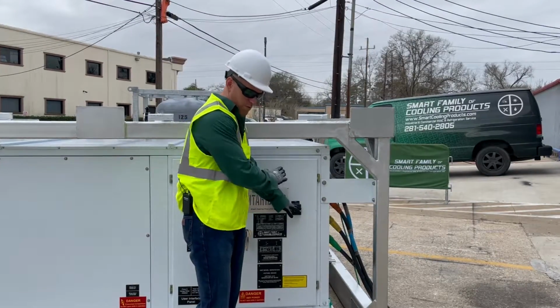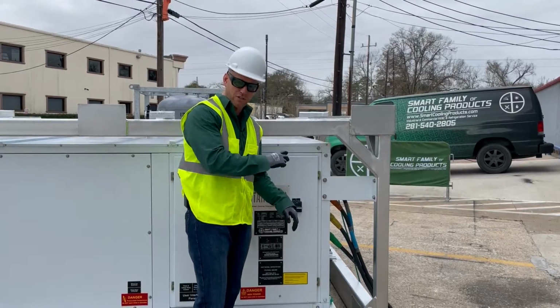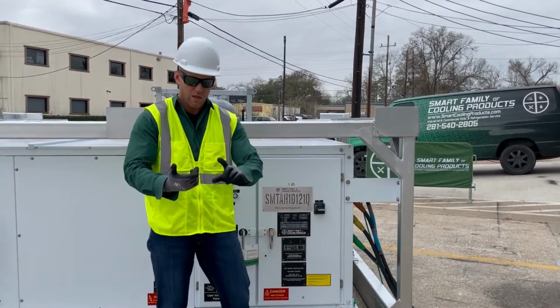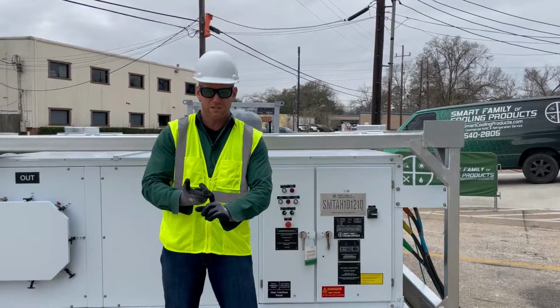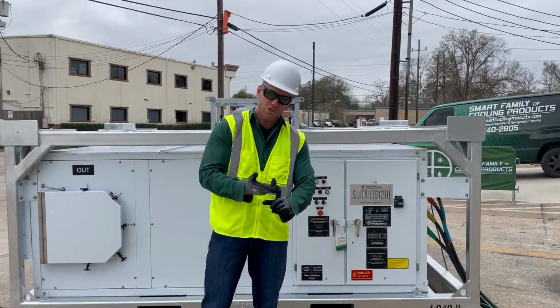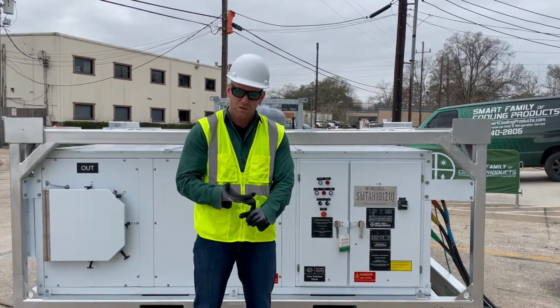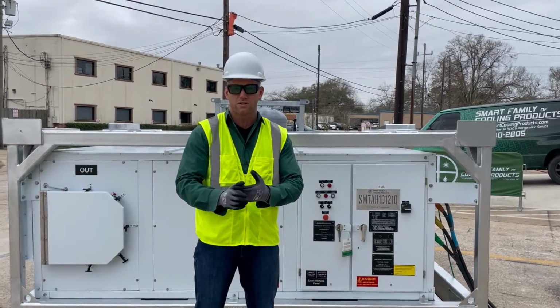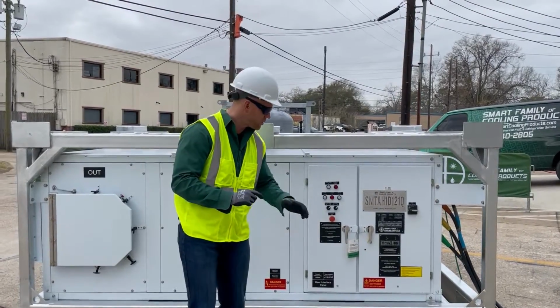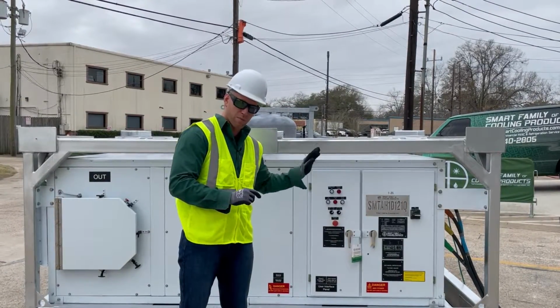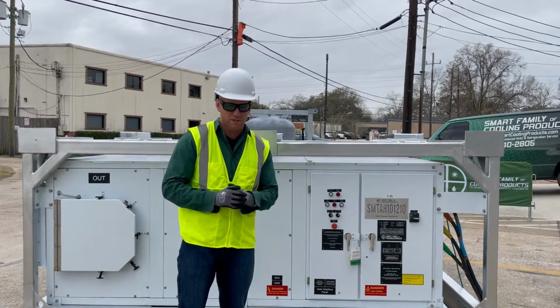Now, there's lots of different means of electrical safety or electrical protection upstream of this unit. That could be a circuit breaker and an MCC, it could be fuses, you could have an I-line panel with circuit breakers, or it could even be a circuit breaker on a generator. However, please note, electrical protection upstream of the unit circuit breaker is your responsibility.